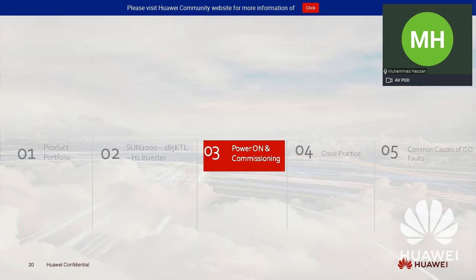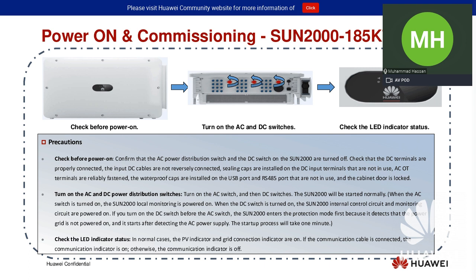Powering on and commissioning of SUN2000 185 KTL. Once you install the product, you need to check a few things before powering on that inverter: that the AC cables are properly installed and properly torqued, the DC switches are all off, and there are no loose connections on the string side.